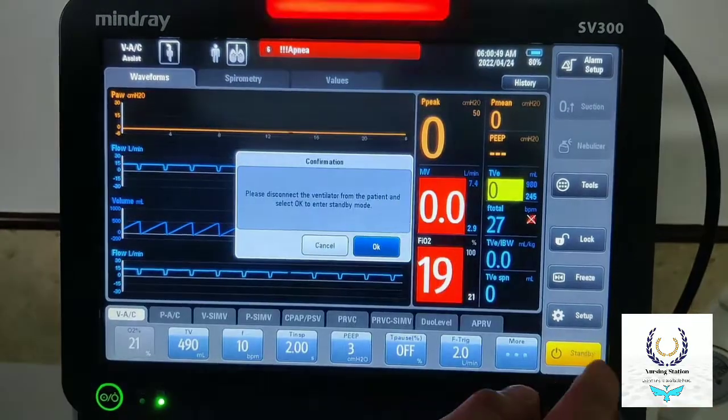While using oxygen supply from the cylinder, first keep the flow on the lower side and then increase the flow manually from the cylinder valve as per FiO2 requirement. As mentioned earlier, we cannot change FiO2 on the ventilator directly in LPO setting, so we have to regulate FiO2 by regulating the flow from the O2 cylinder. If we fail to do so, it may damage the O2 sensor of the ventilator.